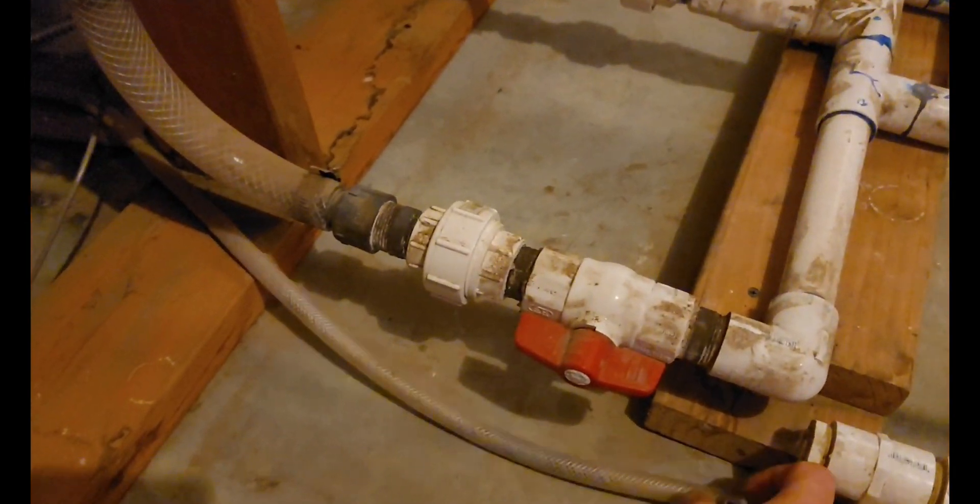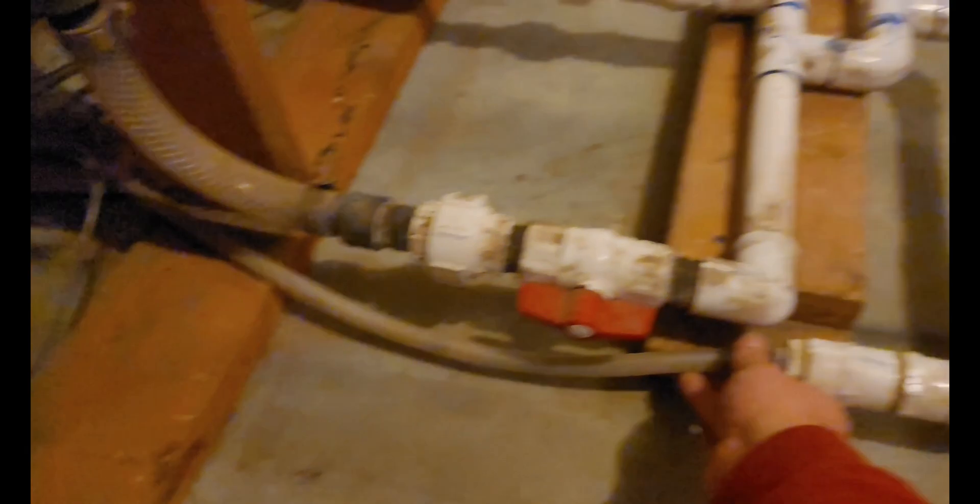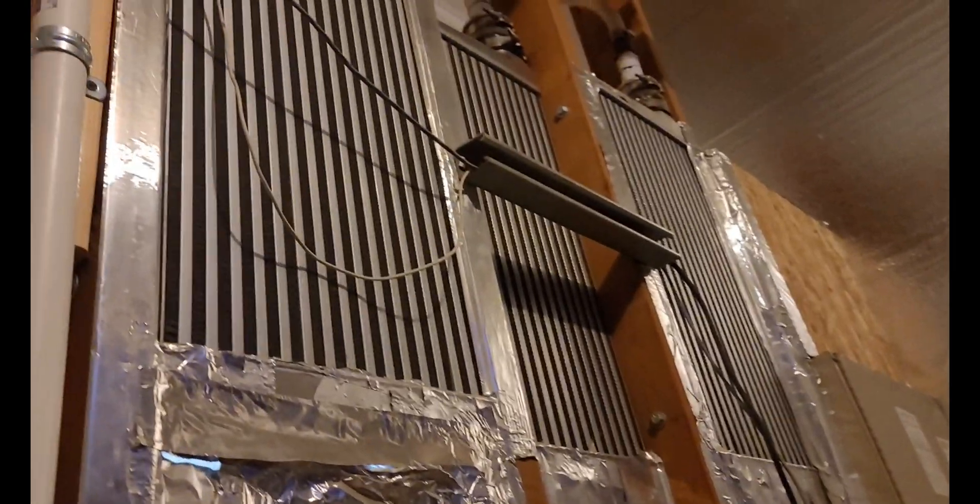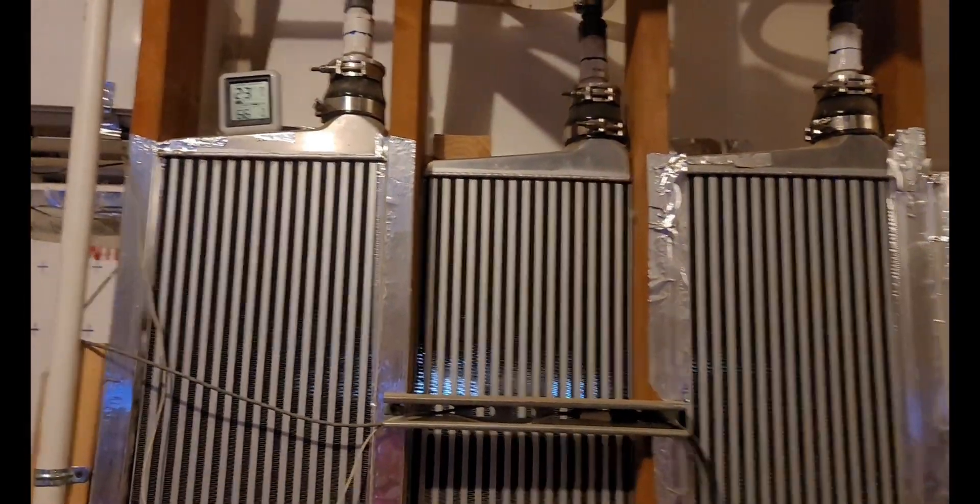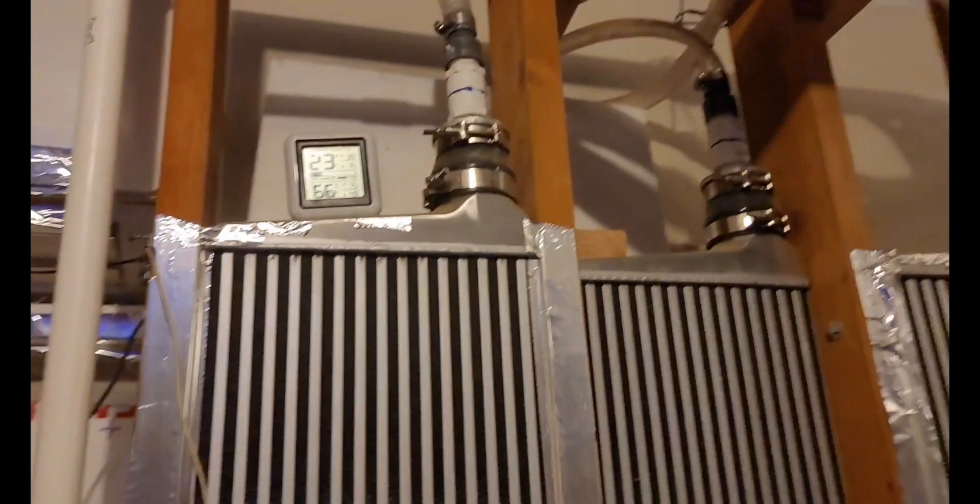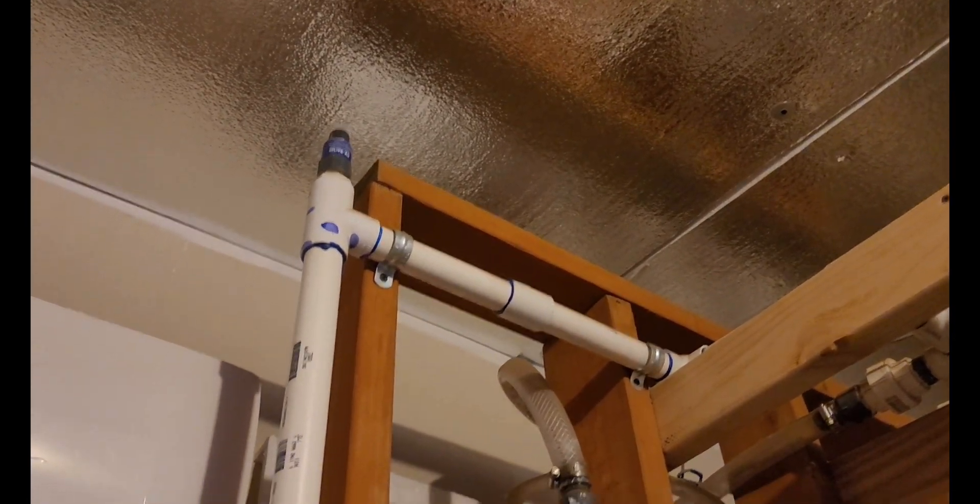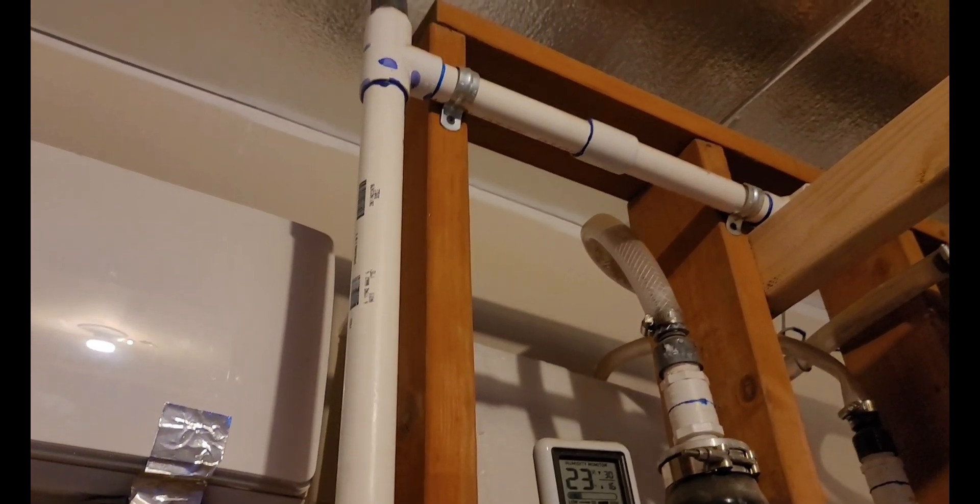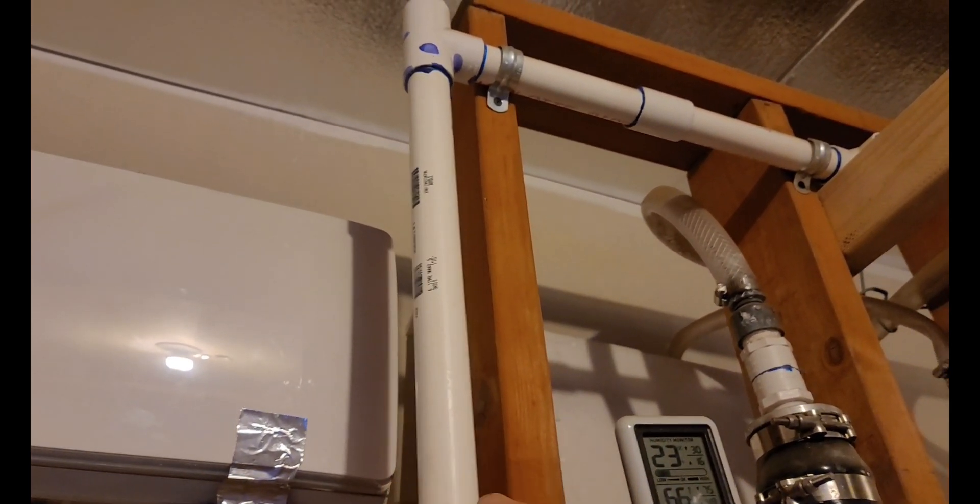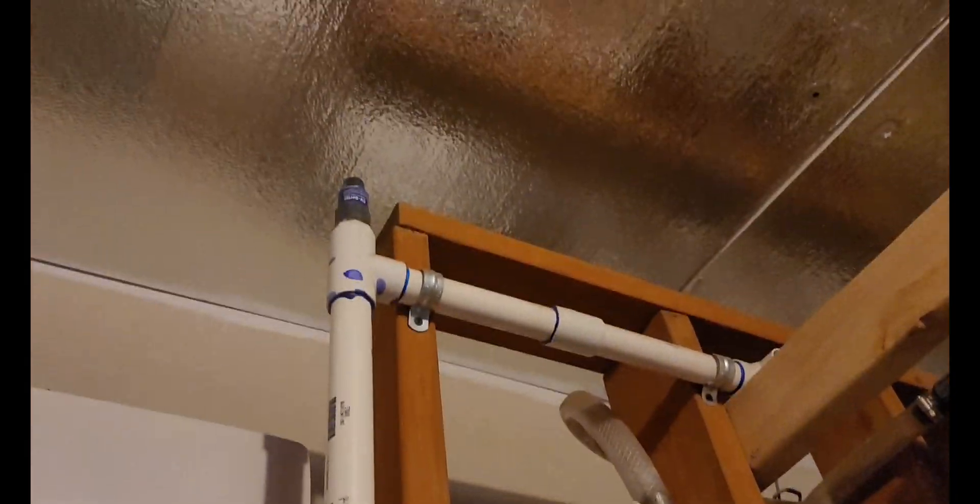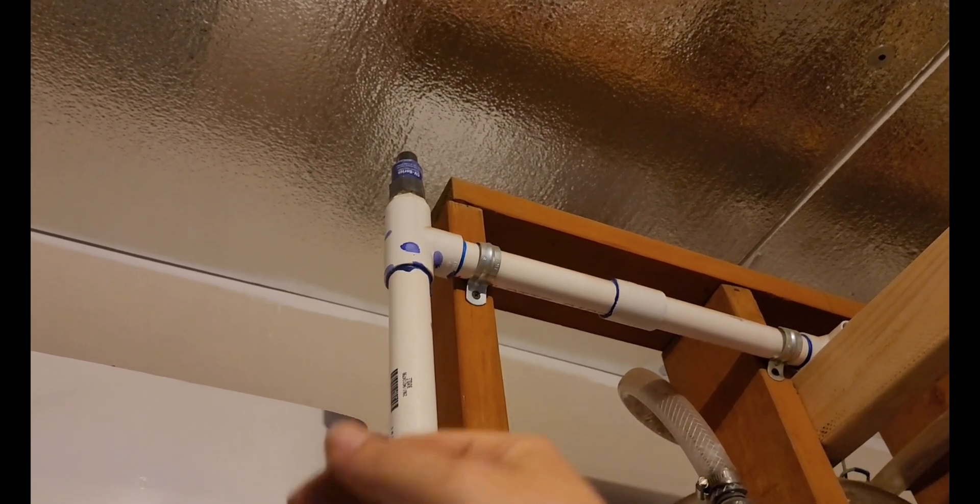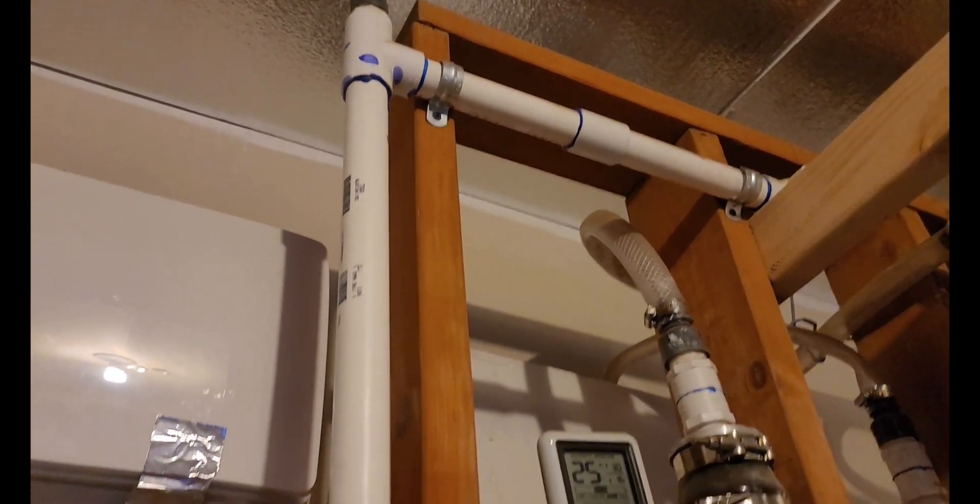The water would come in through here and it would push the heat up and basically evacuate the heat from the intercoolers because heat rises. Once the heat was evacuated from the coolers they would cool down. I got a little vent valve right here because when I shut off the water, the weight of the water would create a vacuum in the intercooler, so I use that pressure relief valve to allow air to come in.